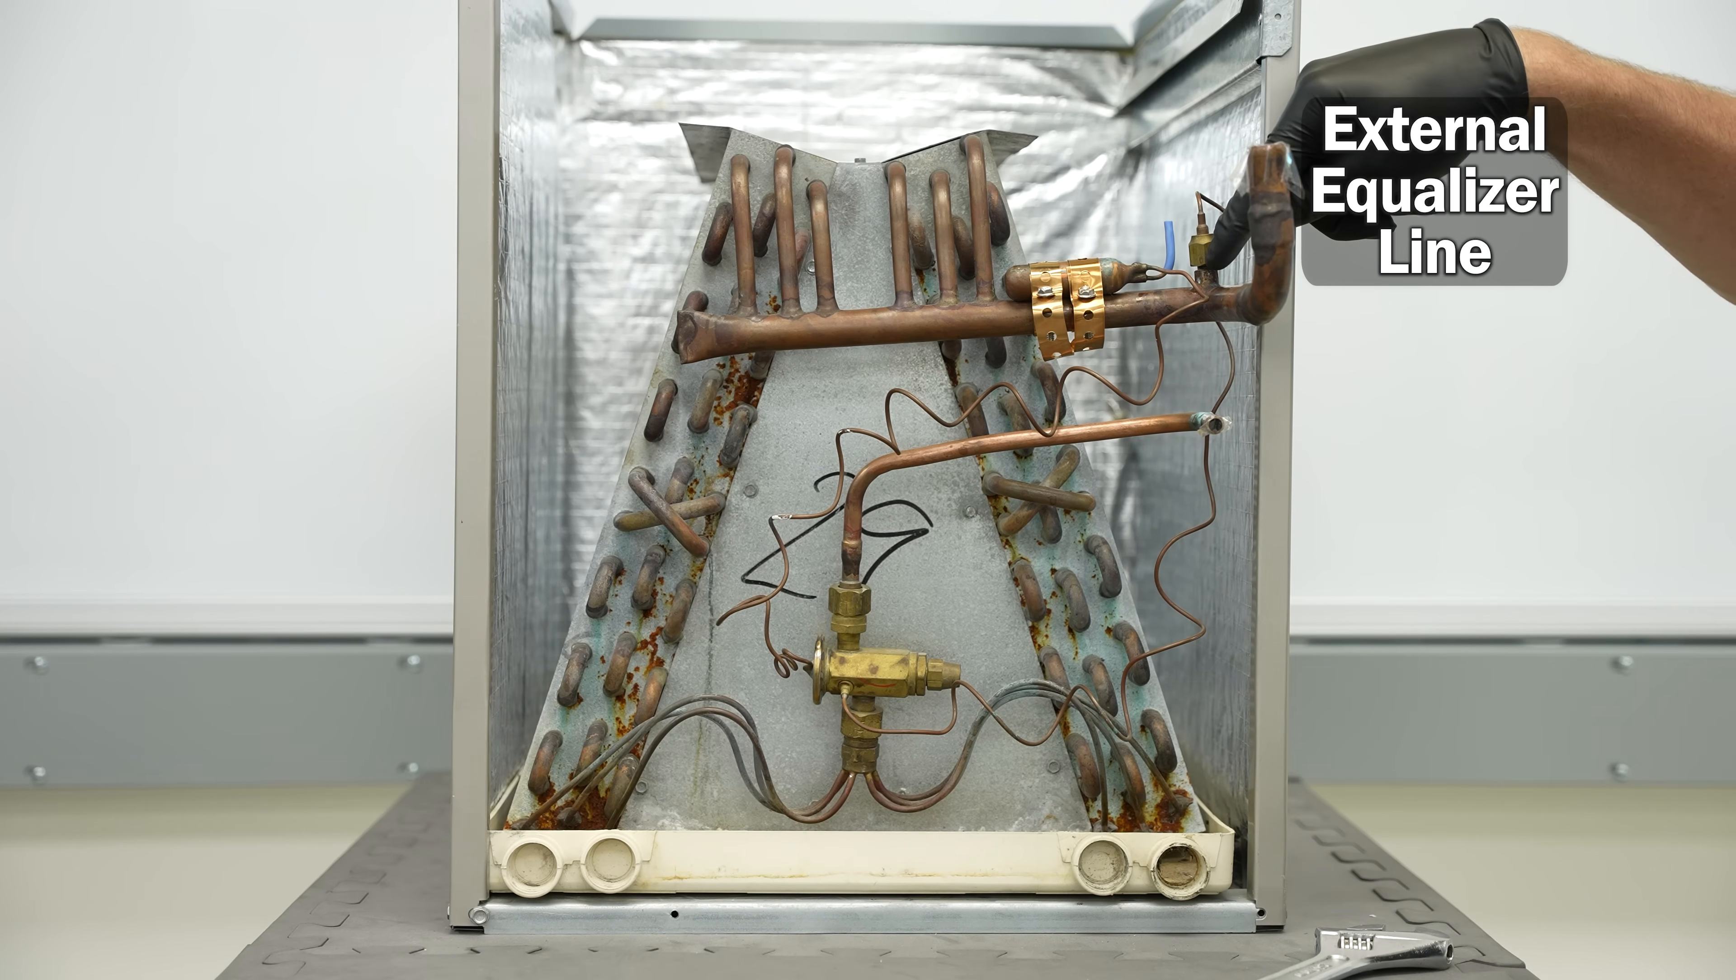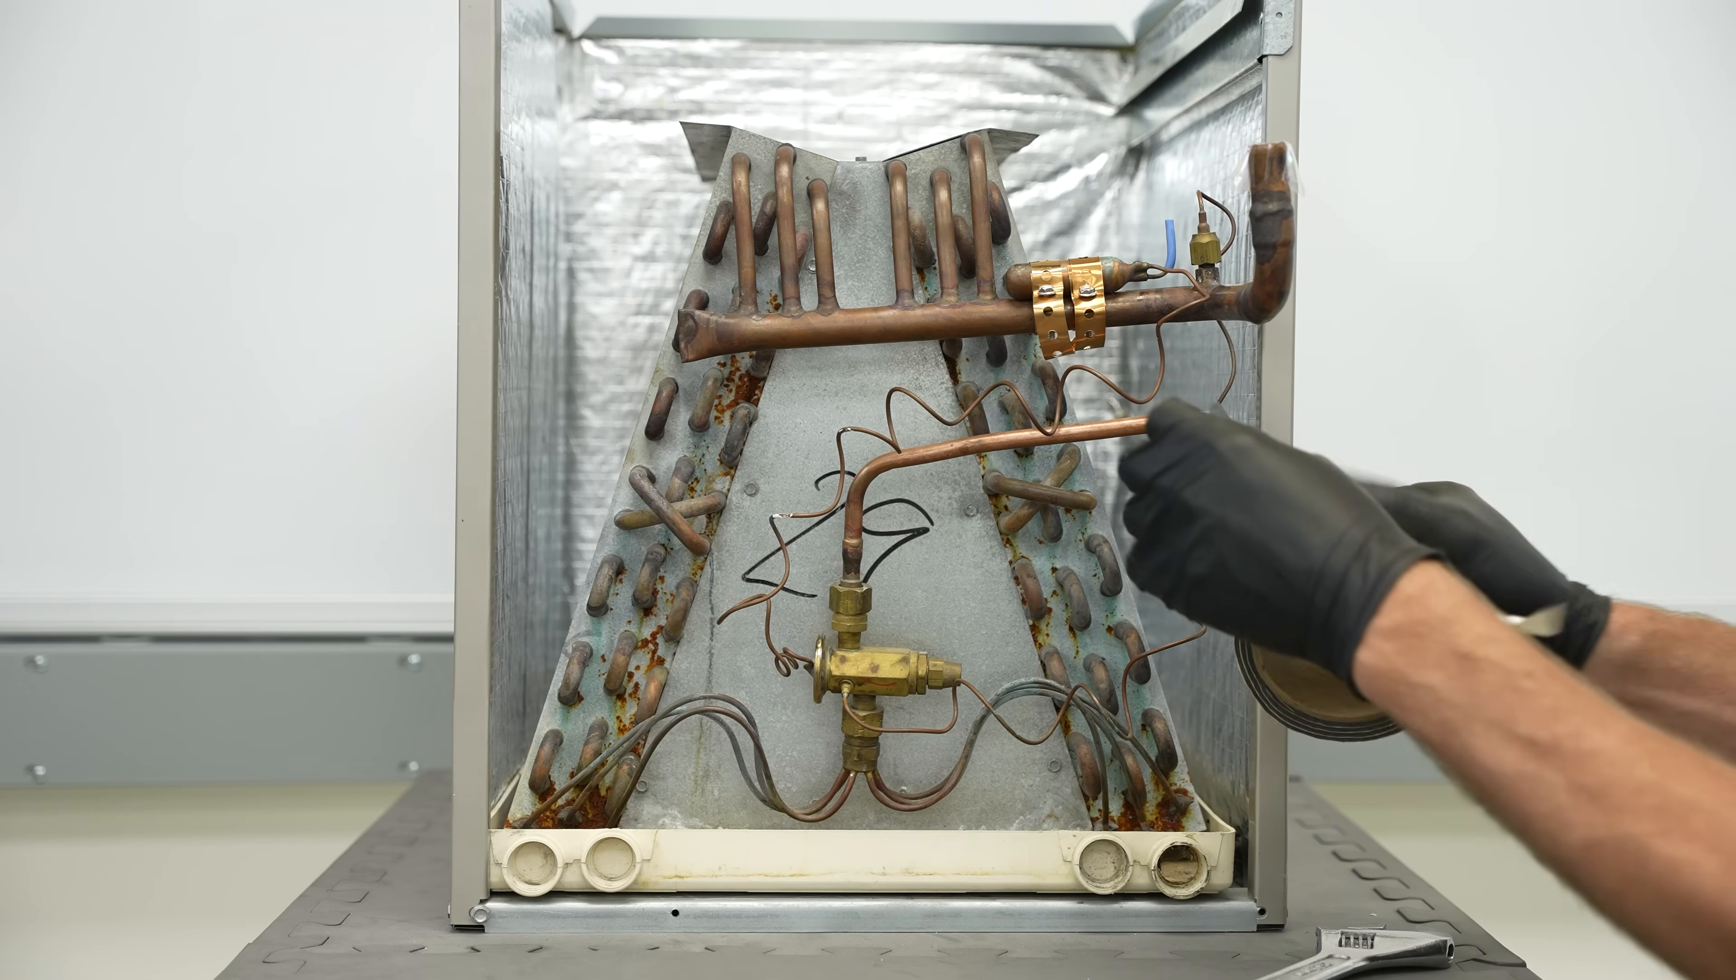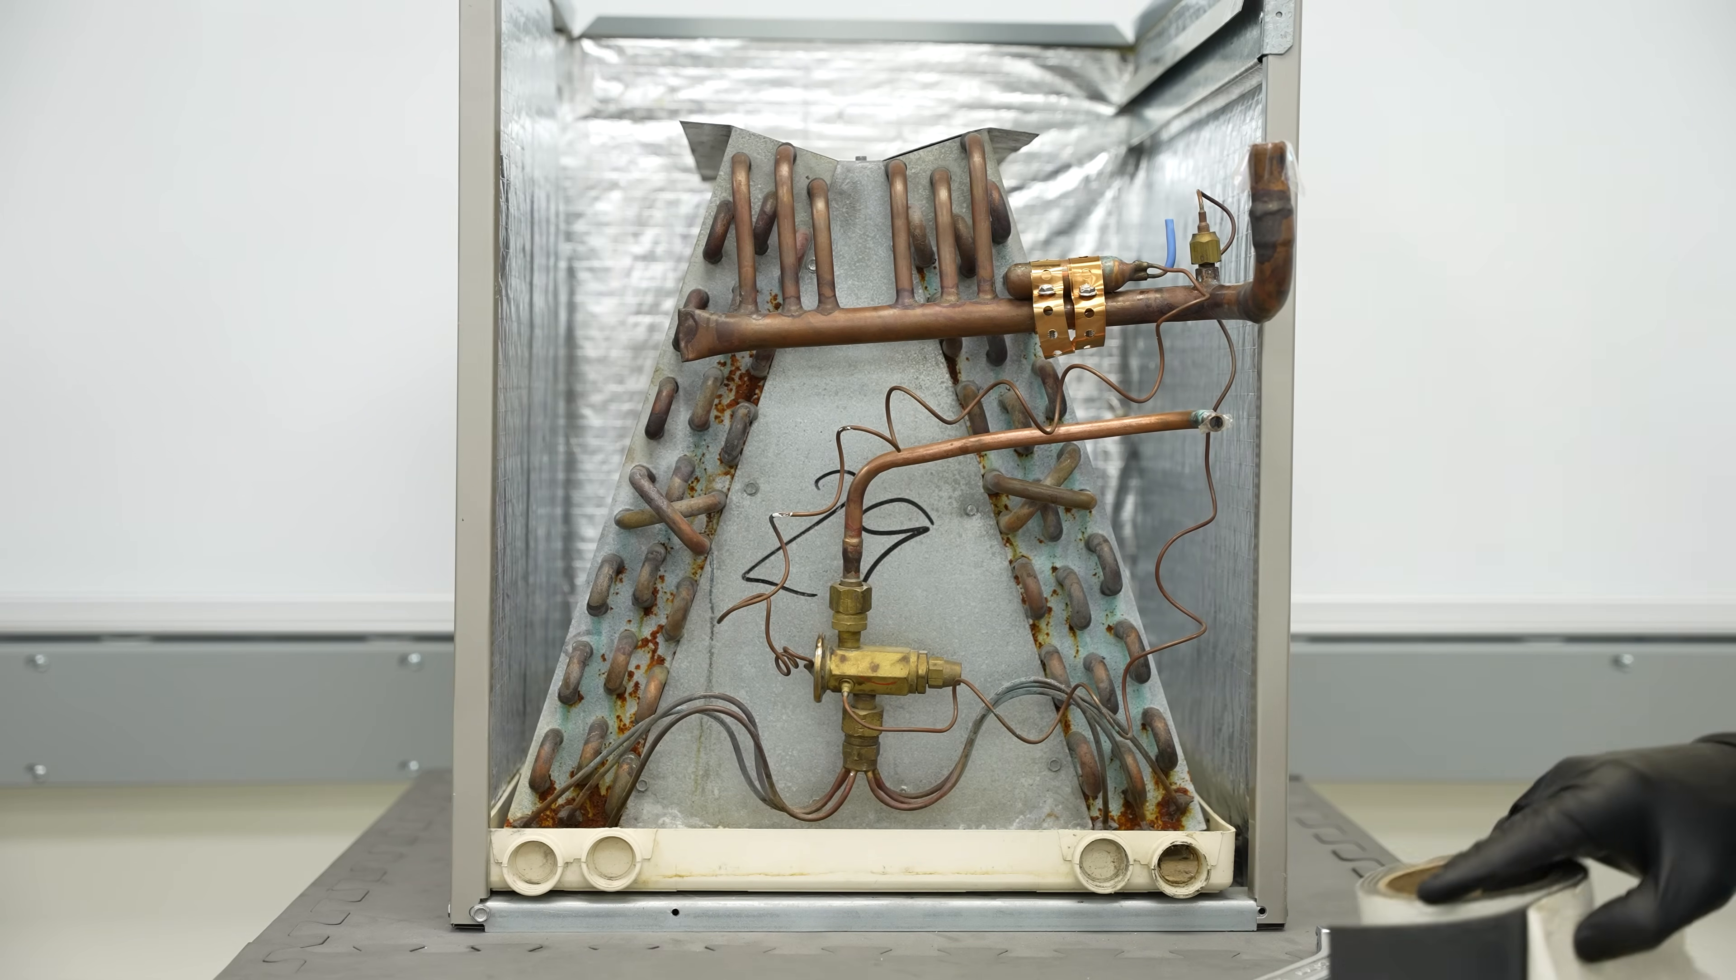I like to have that external equalizer downstream from the bulb, but some manufacturers actually have it before. It just depends. But if you're installing it in the field, you should definitely put the external equalizer downstream of the bulb. After you install the bulb, you're going to want to put insulation around that just to make sure that you're truly sensing the temperature on that vapor line. You can put that tape on and put zip ties on, or you could also use cork tape instead.